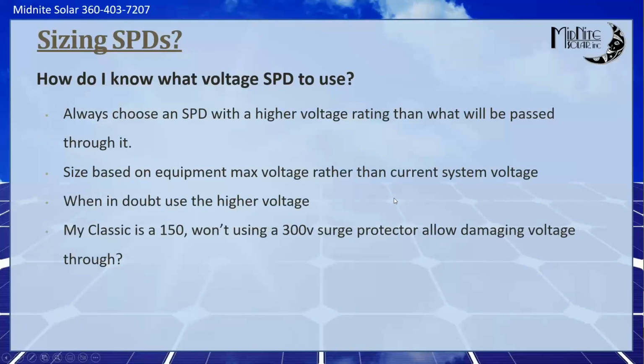So one of the common questions we get is, what SPD do we use? What surge protection device do I use? What voltage? What model? And one of the common misconceptions we get is that people think they need to use the lowest voltage SPD possible because, if I use a 300 on a Classic 150, I'm going to damage that Classic 150.